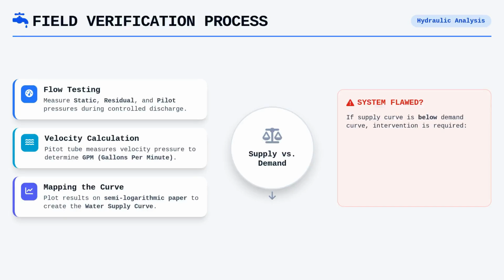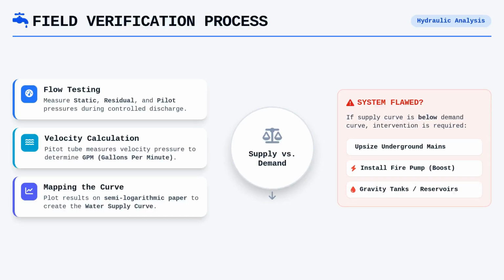If the water supply curve is not sufficiently above our demand curve at all points, the system is fundamentally flawed and requires intervention. This intervention could involve upsizing the underground mains, installing a fire pump to boost pressure, or seeking alternative sources like on-site gravity tanks or pressurized reservoirs.